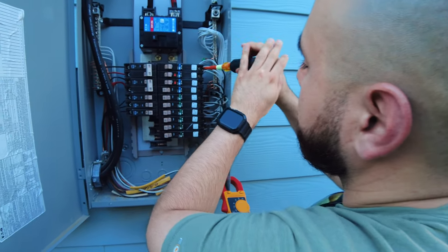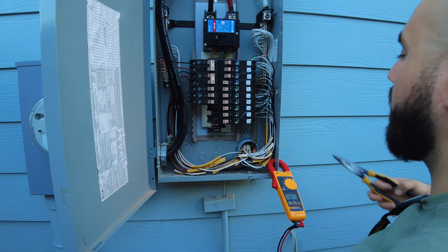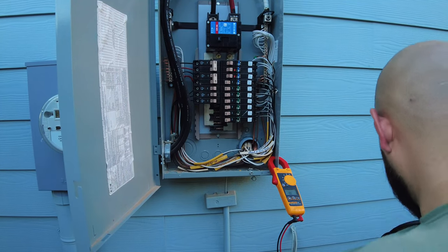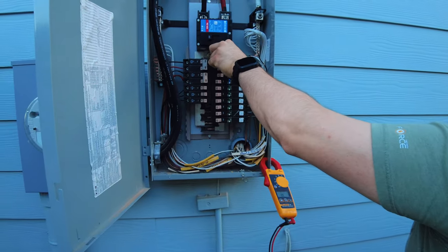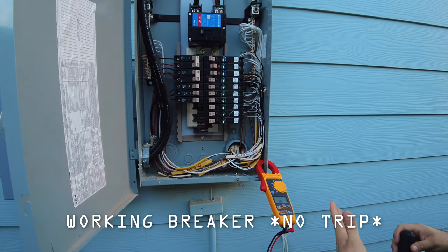So what I did was take the wires off of the breakers — the top-right three breakers. The first breaker was in working order; the second and third ones were the ones that were tripping. By removing these wires I can test the breaker without any wires connected to it, and if it still trips, that indicates that the breaker is bad.